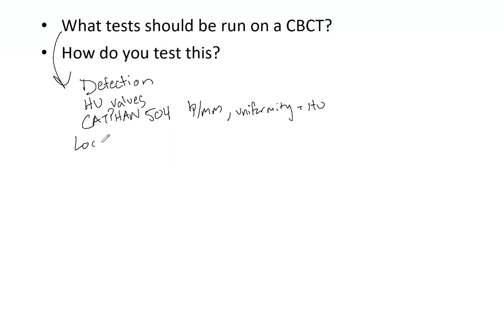You also want to check localization and geometric distortion, as this can happen on cone beam CTs. You have a baseline and know what value should be, so if you see that deviate over time, this is a way to know you need to contact your service representative and have your system worked on. And then the big one — CTDI. This needs to be done once per year, and for one scan, you need to know what dose you are delivering. This needs to stay constant throughout the life of the machine.